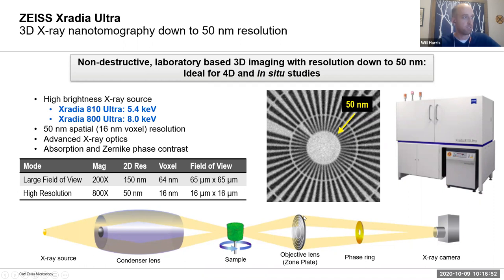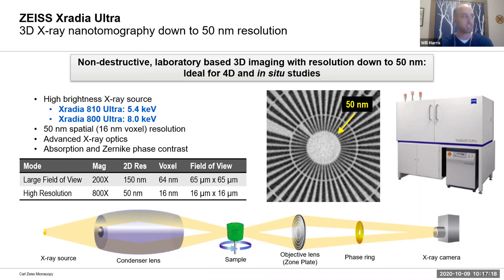The way this instrument works is we add some x-ray focusing elements into it — pretty unique in a lab x-ray tool — namely a glass capillary condenser lens and a Fresnel zone plate diffractive element. The reason for incorporating optics, as with any optical microscopy technique, is you need these to properly focus your beam, and they really are the things that dictate the resolution. By incorporating these elements acting directly on the x-ray beam, you can do imaging down on the tens-of-nanometer scale — here showing 50-nanometer lines and spaces in a star test pattern.